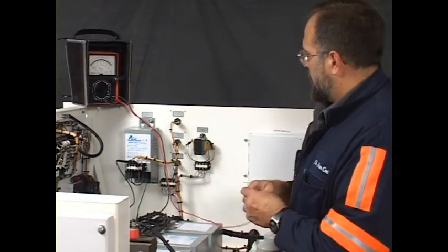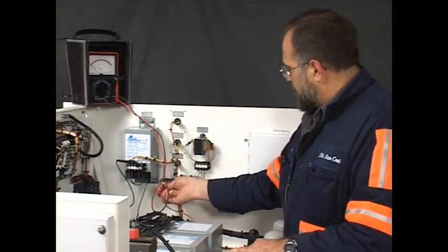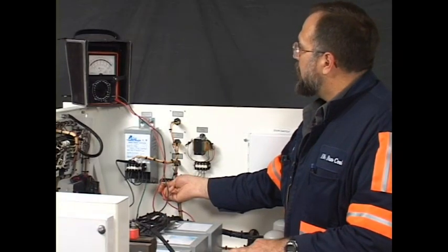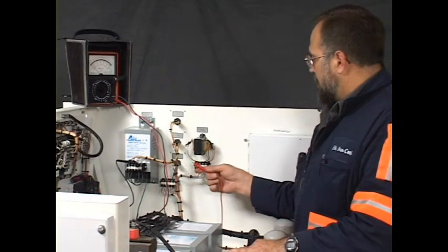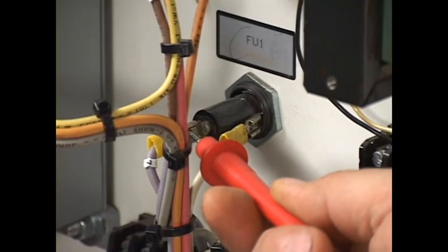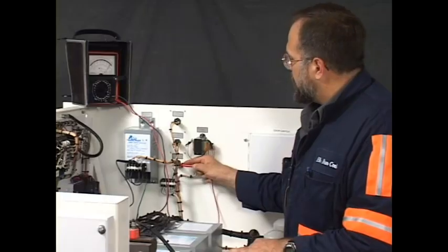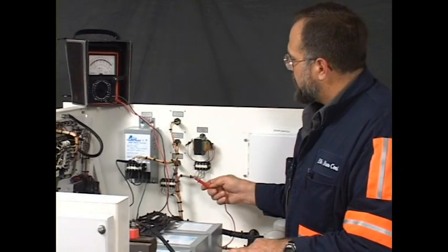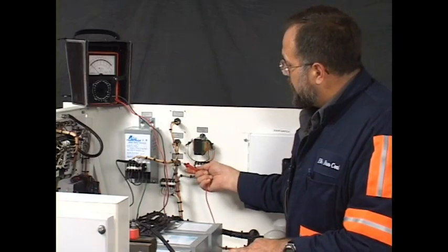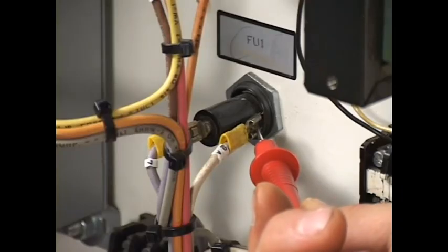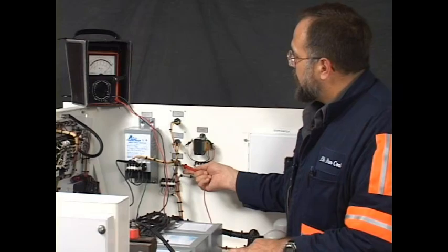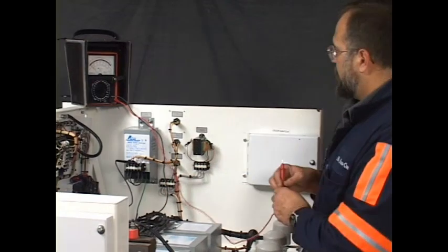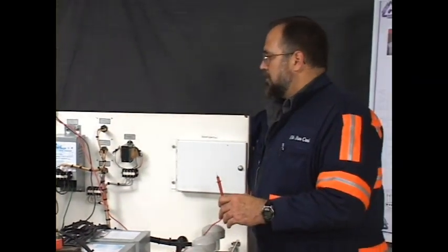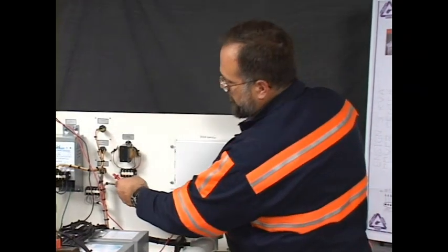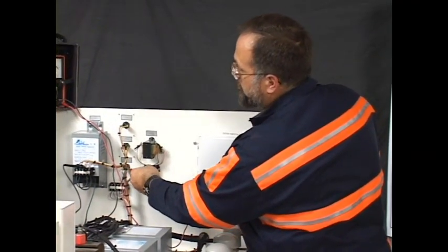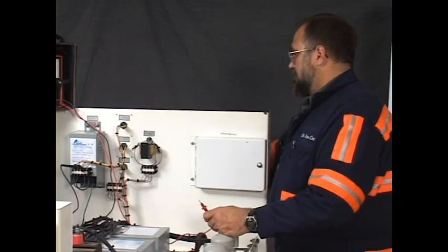And go to the terminal strip. Here we go. We're good. Go to the line side of the control fuse, FU1, wire 7. That's good. Read through the fuse to check the continuity of the fuse. That's good. Fuse is not open. If the fuse were blown, when you read that circuit, it would read this. I'll take the fuse out so you can see. Just read an open. That's a bad fuse.